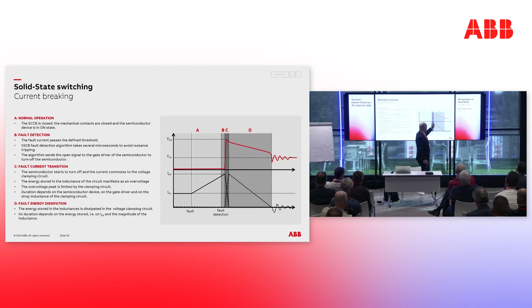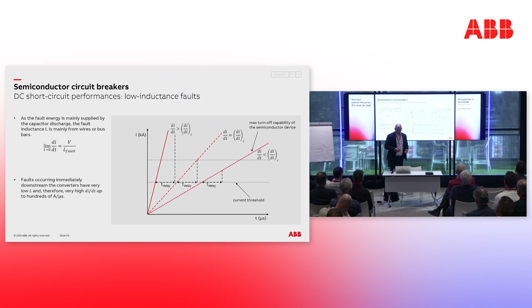One thing I think it's important to take away is that unlike electromechanical circuit breakers, in solid-state circuit breakers, you don't have the same limitations, but you do have one particular limitation, and that's the rate of rise of current. As long as the rate of rise of current is lower than some critical value, it's fine, we can interrupt. Why? Because we notice that we have a problem, we have a threshold, but as I said, we have to wait, or there is some delay between the detection and opening. If the di/dt is too fast, the time delay becomes too long, and the current can hit a value where the semiconductor can no longer interrupt the current in a controlled manner. Inevitably, every semiconductor I know will at some point act as a fuse, but an expensive fuse. So that's not what we want, right? And that's why di/dt is so critical.